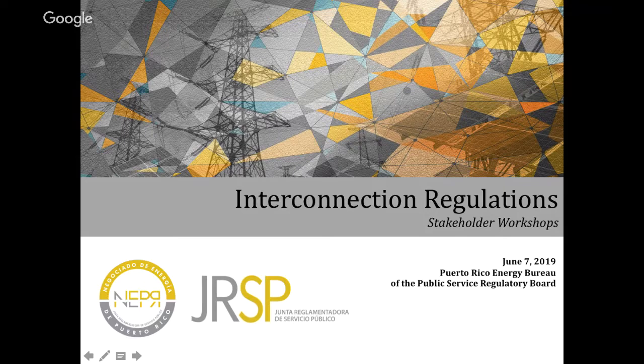When we enter into the technical considerations, mostly three things: if when we interconnect equipment to the public grid we cause voltage problems, if we go beyond the voltage limits. We know ANSI has very strict limits as to how the voltage needs to be, and it's not capricious or whimsical. It's specified that way because if you go beyond that voltage, you begin to burn transformers and the surge arresters I have in the grid to protect the system.